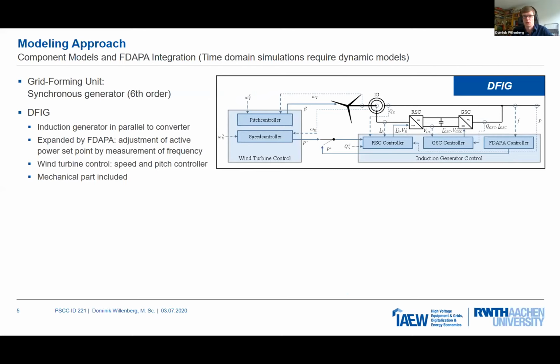So concerning the modeling approach, first of all, to operate an island microgrid, it is necessary to have a grid forming unit. In that case, a synchronous generator of 6th-order model is used, of course, with the necessary controls concerning exciter and governor.